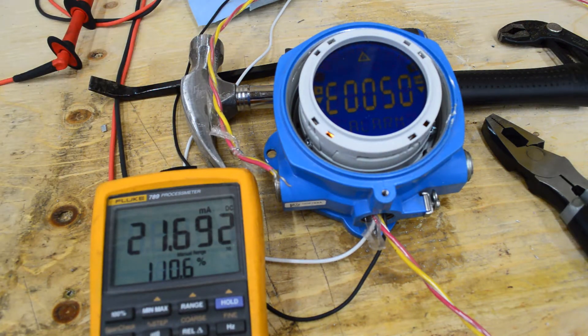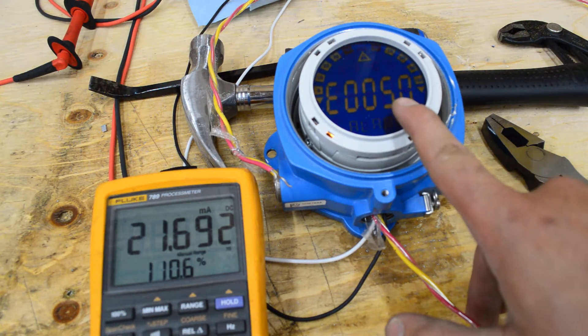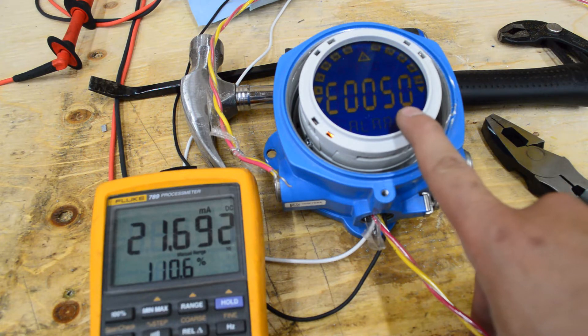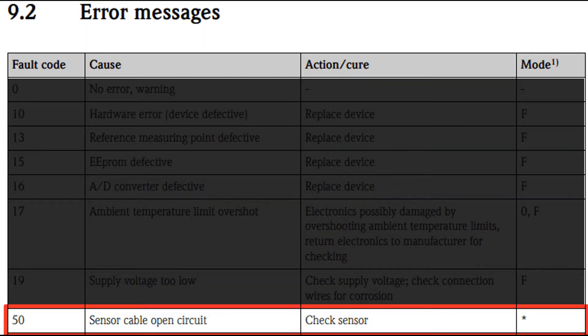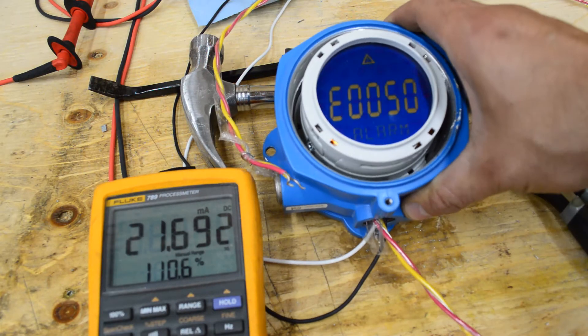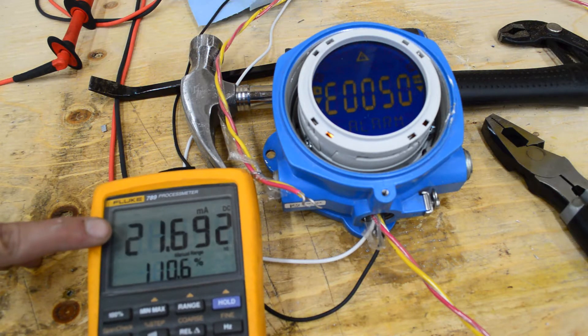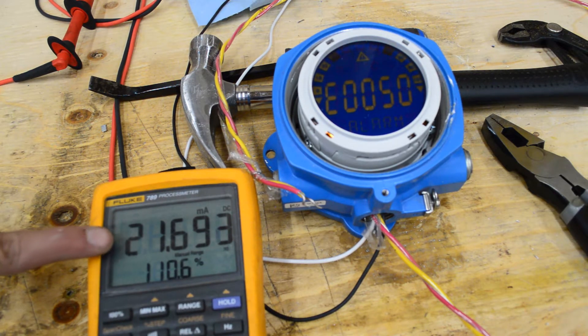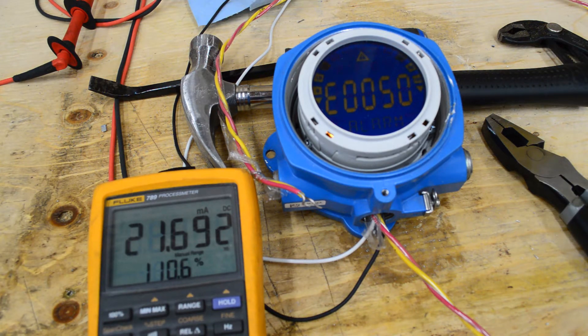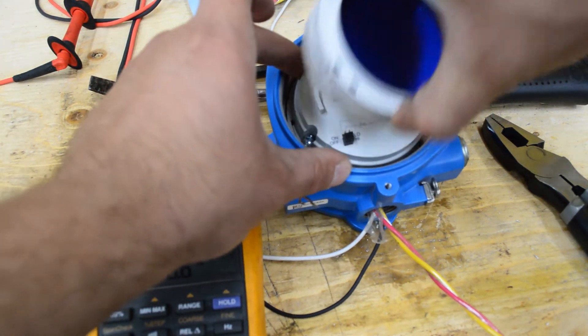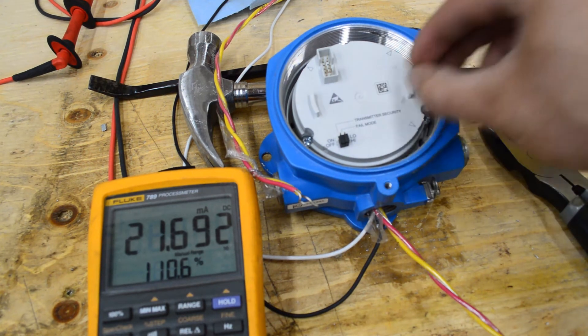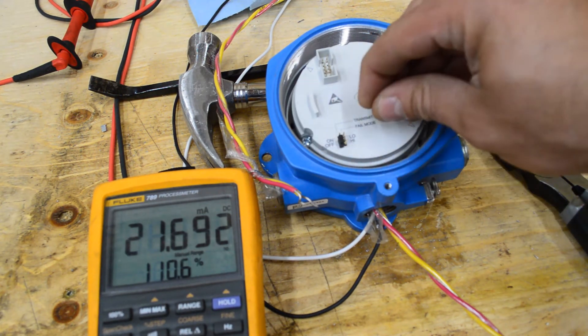And there should be an error message showing up on here too. So, yeah, there we go. So that must mean that is their open circuit error code. And it's currently in an alarm state. And it's putting out more than 20 milliamps which would generally be a fault.